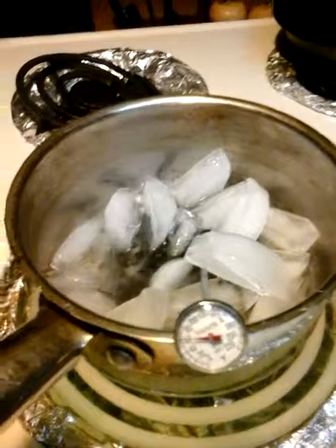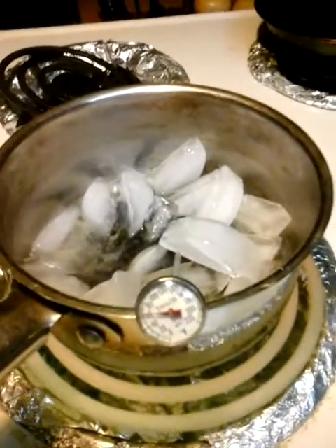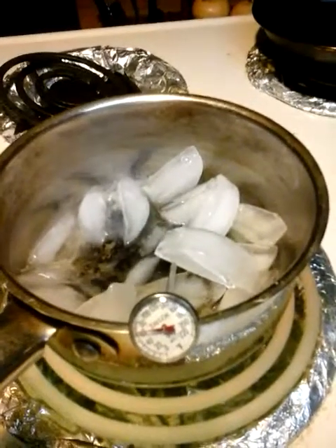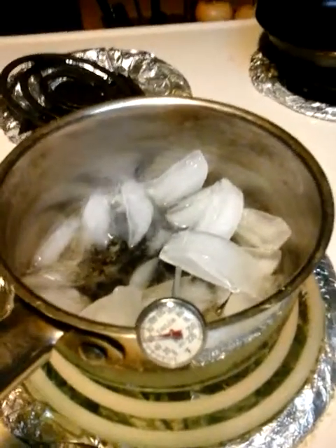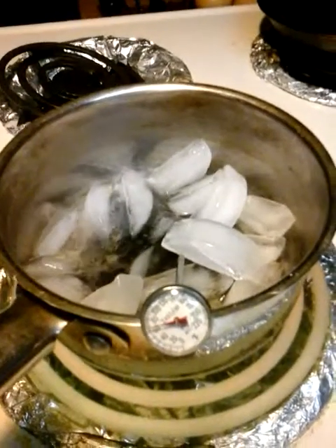Same thing is happening in your evaporator. The majority of your freon, like R22, changes state. A 40 degree evaporator starts to boil off the freon to become low pressure, low temperature gas. It doesn't require 144 BTUs because it's under pressure in your evaporator.